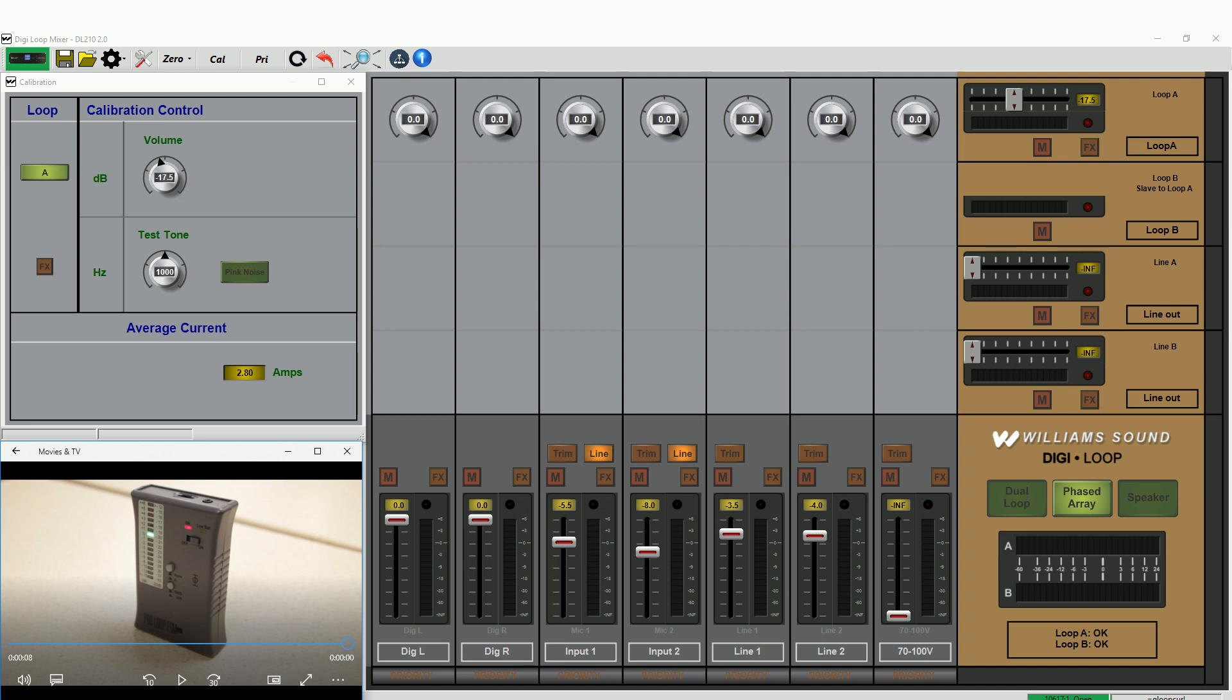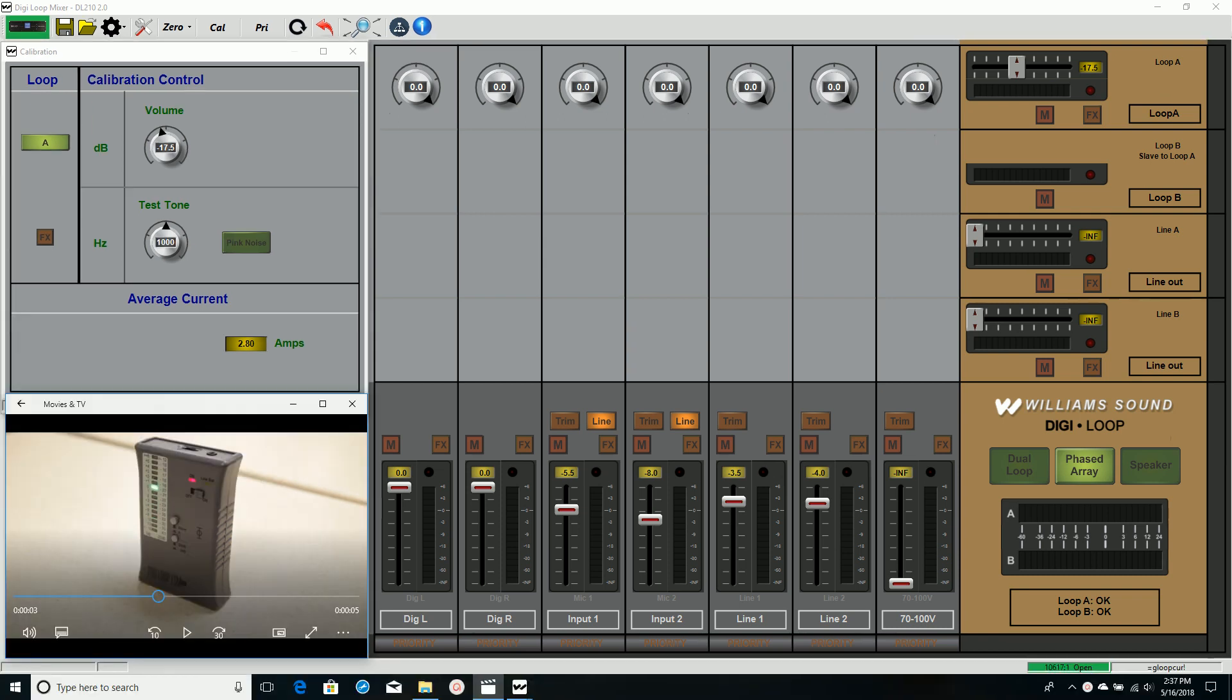It specifies that the field strength must be 400 mA/m plus or minus 3 dB at 1 kHz across the entire looped area. I'm going to assume the loop wire is installed, tested for continuity, it's hooked up and meets the load requirement of the amplifier.